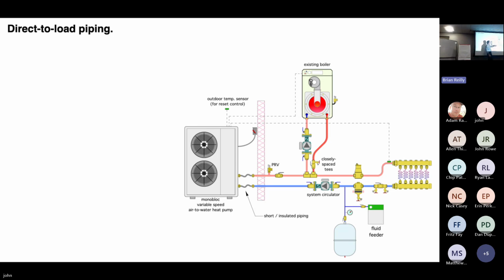And it senses it based on temperature rise. For example, if I just turn several zones on, I'm going to have a cooler stream of water coming back initially. And inside the heat pump, it's measuring supply temperature and return temperature. If it all of a sudden sees that delta T open up, it's going to increase the speed of the compressor and vice versa. The benefit of this is that there's no buffer tank. And one of the companies, and it's Enertech Global, if you check out their hardware, they stress that their heat pump does not require a buffer tank.